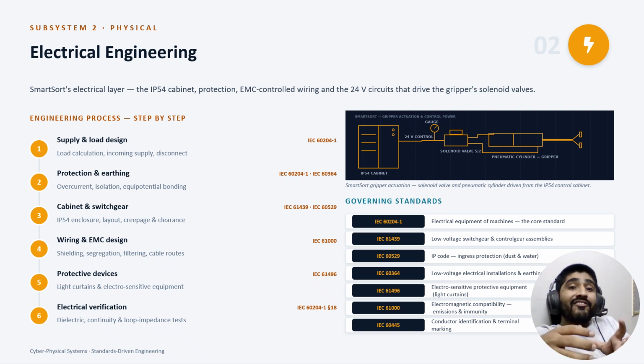Stage number 4, wiring and EMC under IEC 61000. Power and signal cables are segregated, shielded, terminated properly. Why does it matter so much? Because this is the true cyber physical twist. Noise that corrupts an encoder or a valve instantly becomes a physical fault. A gripper that fires at the wrong moment can completely destroy the system.